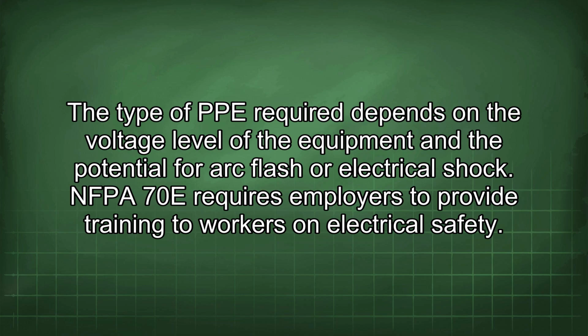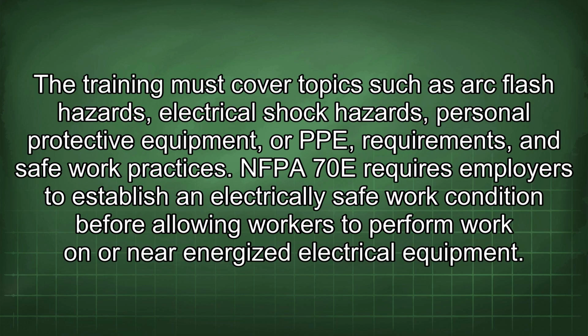The type of PPE required depends on the voltage level of the equipment and the potential for arc flash or electrical shock. NFPA 70E requires employers to provide training to workers on electrical safety. The training must cover topics such as arc flash hazards, electrical shock hazards, personal protective equipment, or PPE requirements, and safe work practices. NFPA 70E requires employers to establish an electrically safe work condition before allowing workers to perform work on or near energized electrical equipment.